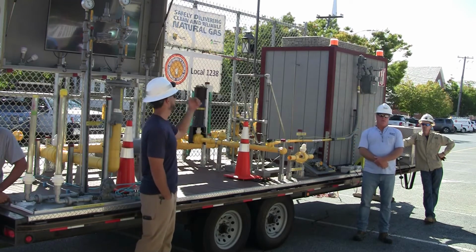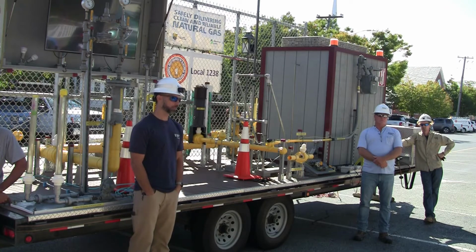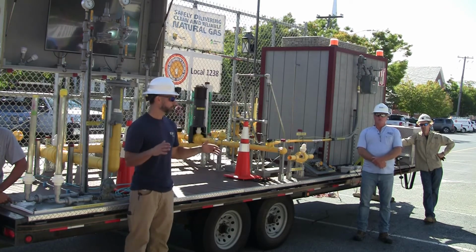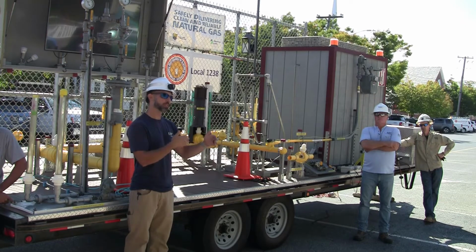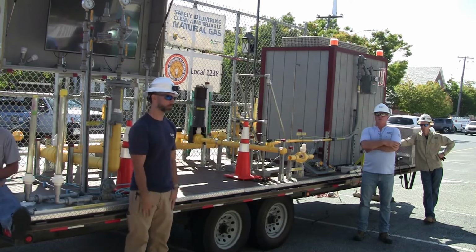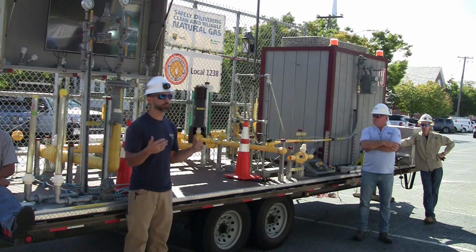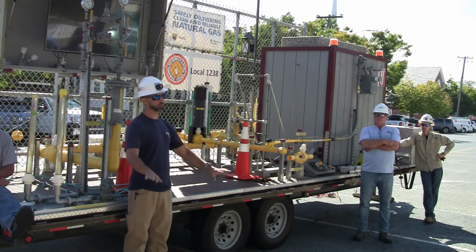Well, if we're going to do some kind of burning, or if you had a break like that, like somebody dug it up, we normally cone everything off. We make sure everybody's away. I mean, we try to. For us, you can't get in the zone of the gas without FR on within 6 to 10 feet. So we try to at least keep people back 15, 20 feet away from where we're at. Once you get within 10 feet of the actual hit, you have to have full FR on and our whole PPE process. So we like to push people at least 20 feet away.